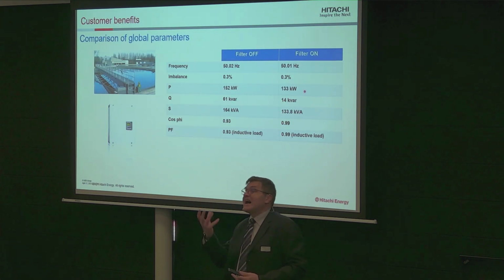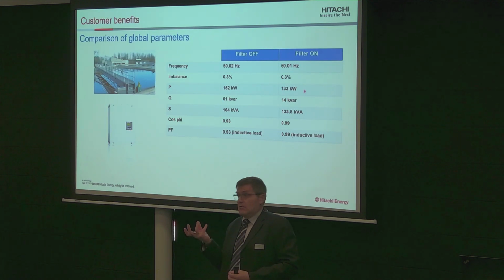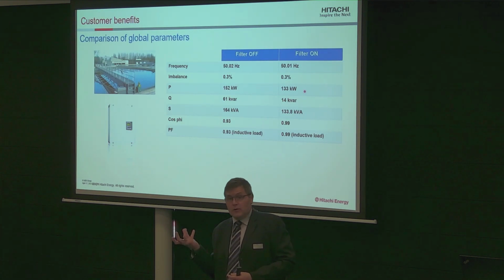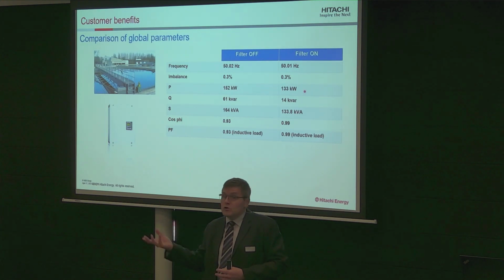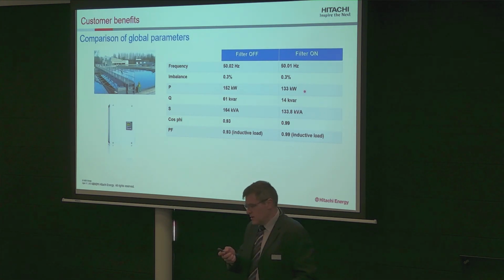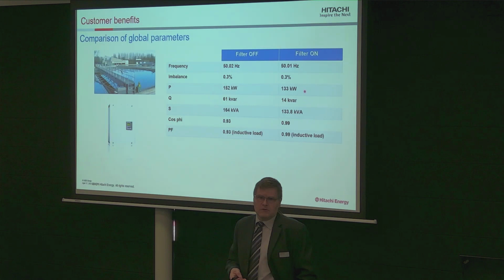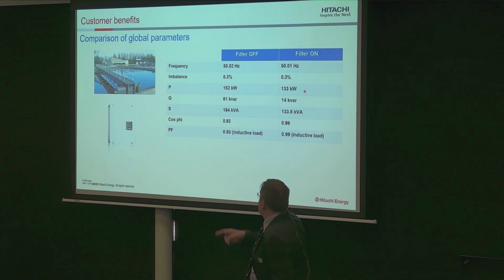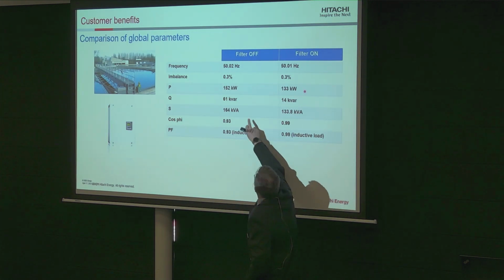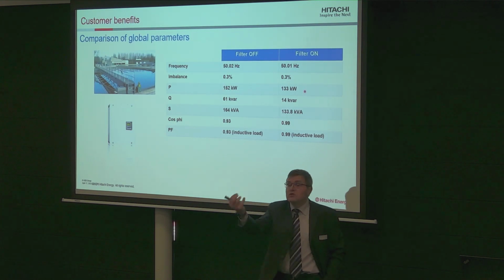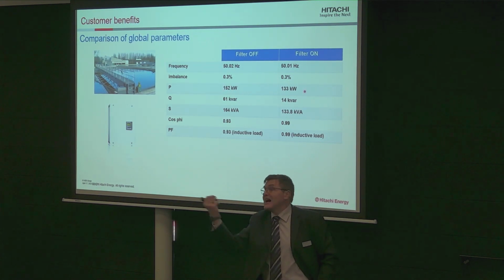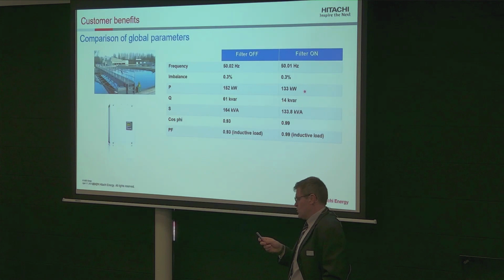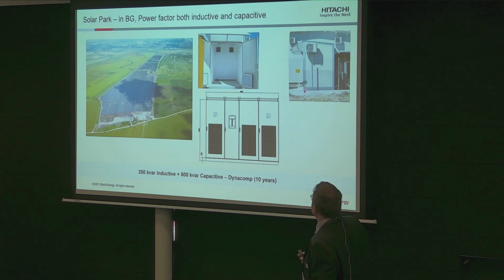It's only the harmonic content, which is purely reactive power, which needs to be addressed. But harmonic, it's at harmonic 5th, 7th, and so on, so not at fundamental. And so this is a very common mistake to still specify a capacitor bank, which will never switch on or switch off. You need an active filter. And then you are going to reduce the number of kVA because simply you reduce the current, you reduce the harmonic contents. Okay, just a small comment.